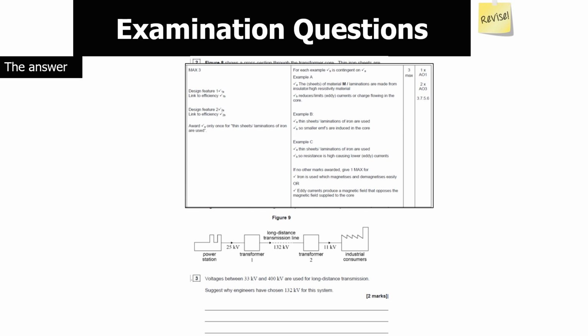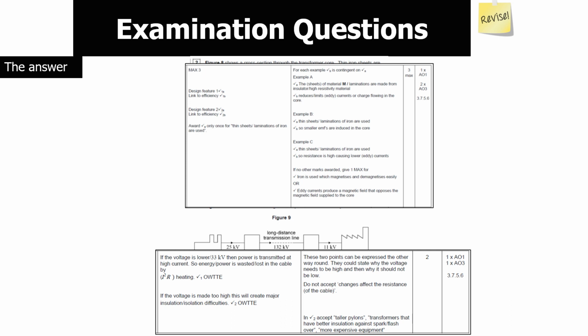Now the next question: why would you use 132 kilovolts for this system? You've got to compare different values, because if the voltage is lower than 33 kilovolts, the power transmitted is at a higher current. Remember V and I are inversely proportional in a transformer, so when V goes up, I goes down, and vice versa. The power loss in a cable is P equals I squared R, so an increased I means increased power loss. That's why we don't want the voltage any lower.